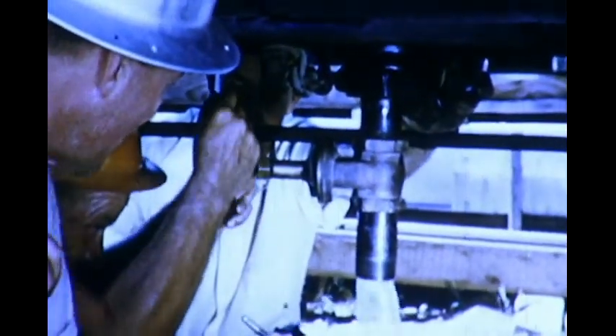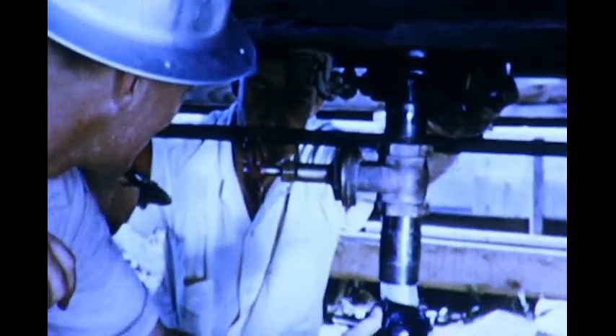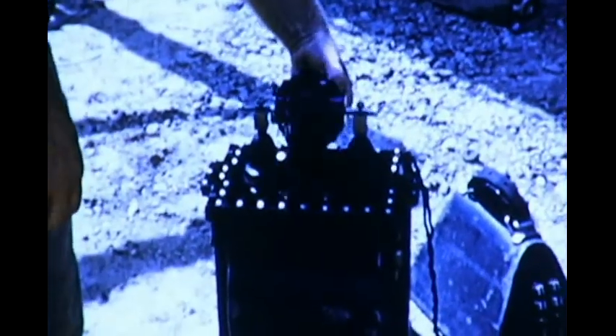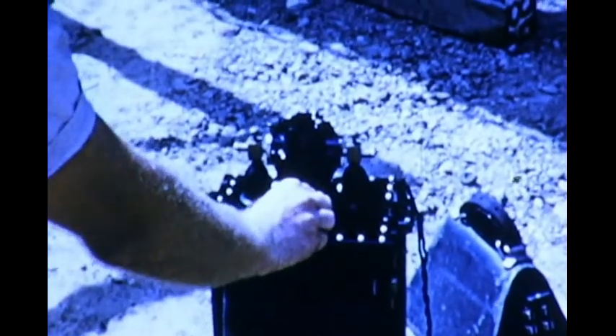Transformer oil brought in by tank car on the Delta Station siding serves as both insulator and coolant and must meet rigid specifications. A small amount of oil is allowed to run out of the tank car through a coupling and valve installed at the site, and a sample is taken for testing. Voltage is increased at the rate of 3 kV per second until breakdown occurs, and with a dielectric strength of better than 22 kV determined, we're ready for the filter press.